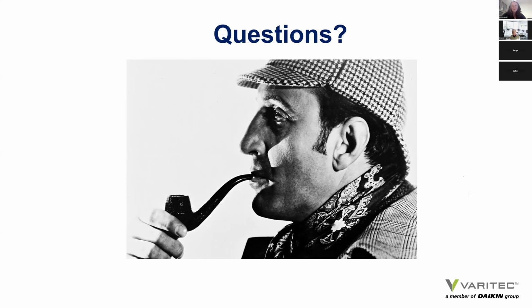Yeah. So what is the plan for including this into the rest of the year in the webinars? We're going to keep the guideline in mind when we're actually addressing air design systems and continue to bring language when appropriate into control concepts regarding 100% outside air systems, VAV systems, and see what we can do to continue to re-engage with this language in the presentation so that we start making ourselves more familiar with how to apply it effectively and to offer more productive conversations with our manufacturers to make sure that we are addressing the sequence issue with our design engineering teams. Perfect. I can't wait to hear the rest of your webinars this year.